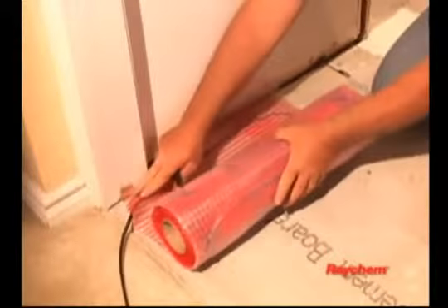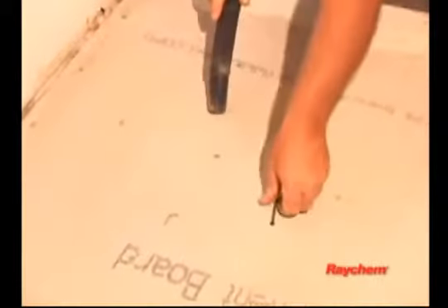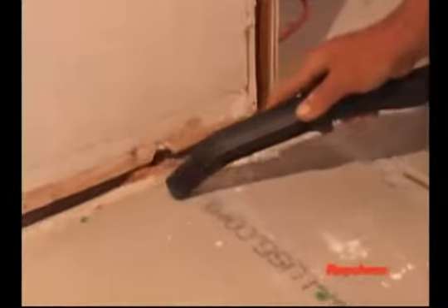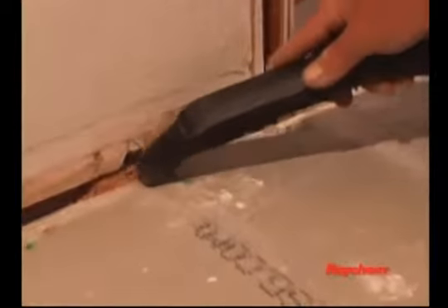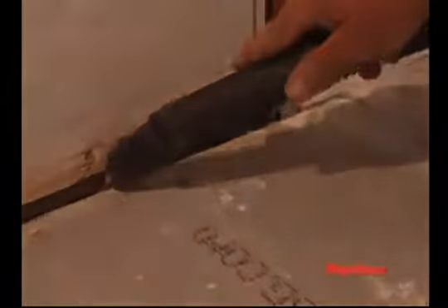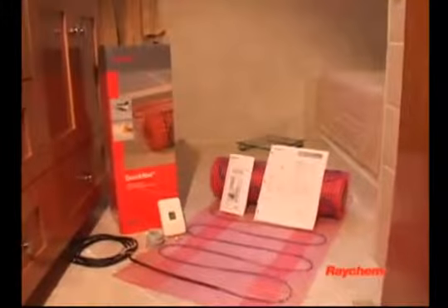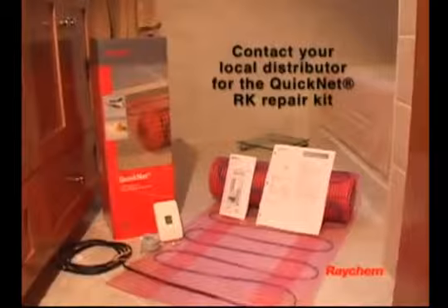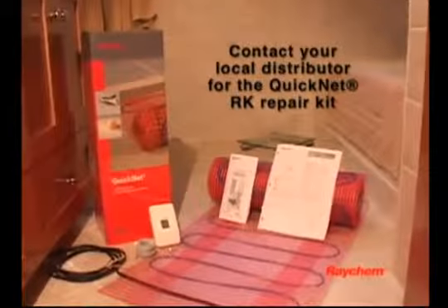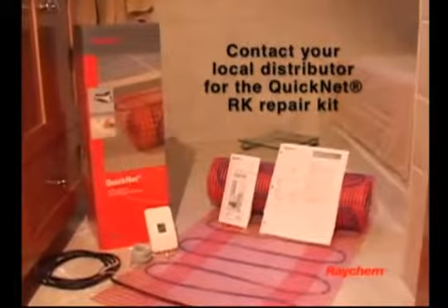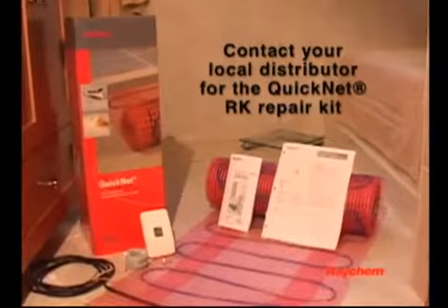Electric wiring and the heating mat will be installed in the floor. Be sure that the floor is not penetrated by nails, screws, and debris that can cause damage on first installation or during subsequent floor repairs in the future. If the QuickNet system is damaged during installation, contact your local distributor or the place where you purchased your QuickNet system for the QuickNet RK repair kit.